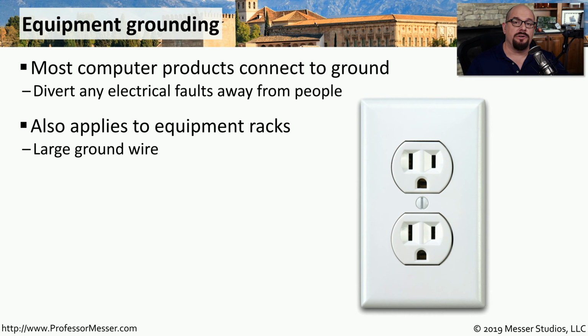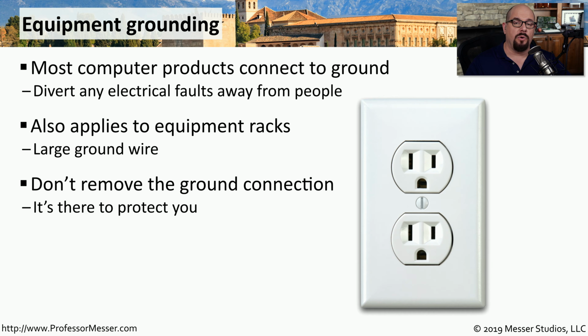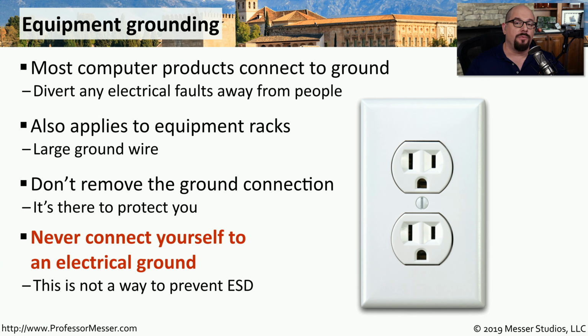If you're in a data center, you'll notice the metal equipment racks are also grounded, so if any voltage finds its way onto the rack, it goes directly to the electrical ground. This ground is important for safety, and you never want to remove these electrical ground connections.